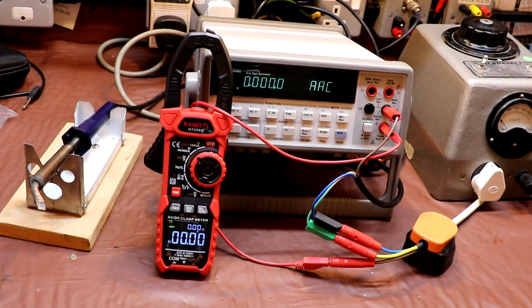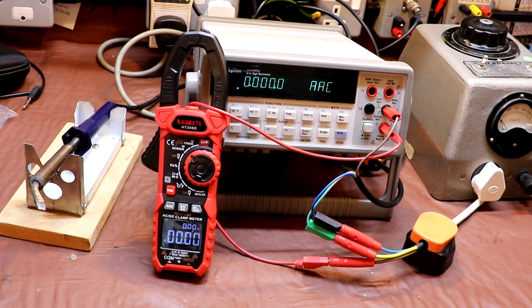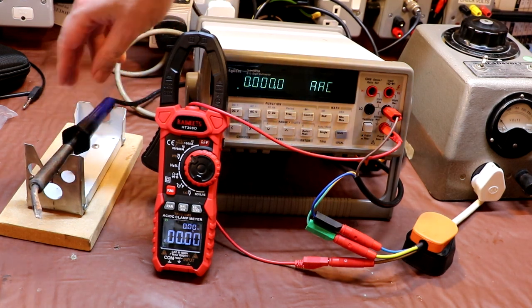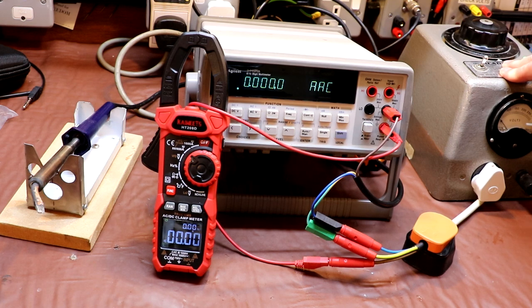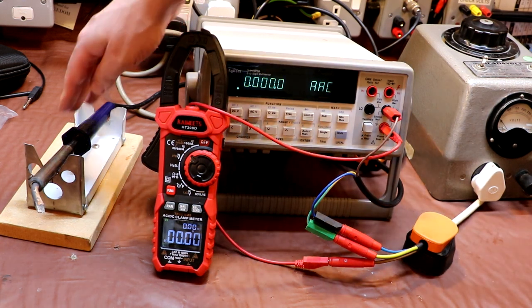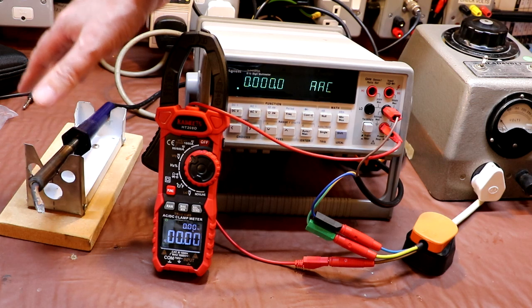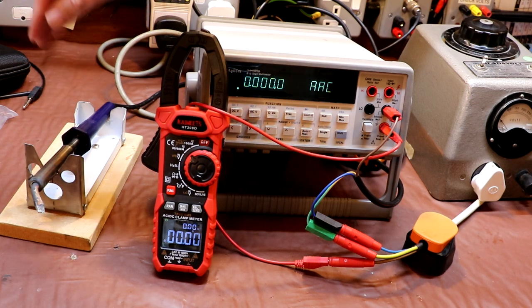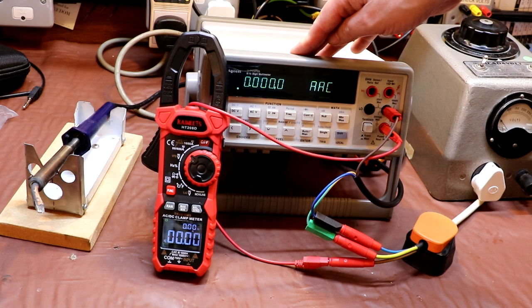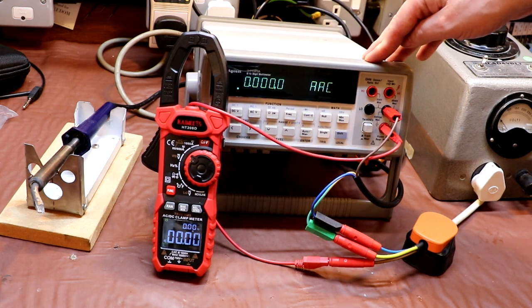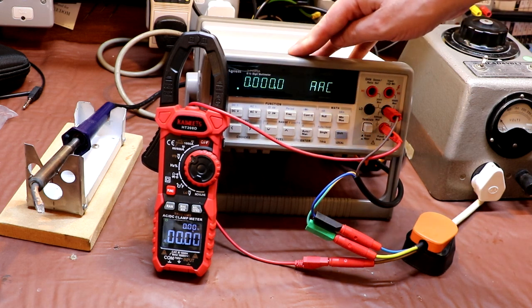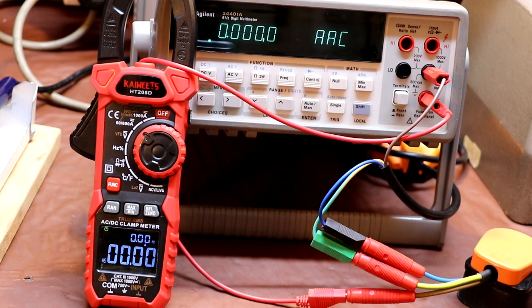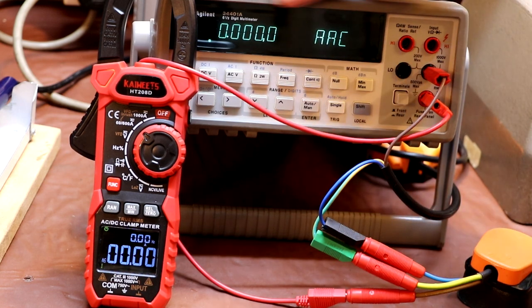I think we'll start off by taking a look at the very lowest AC current measurement that we can make. Now unfortunately I don't own anything as advanced as a current calibrator, so what we're going to do today, we're going to use this soldering iron as a load, and we're going to feed that load through a variac here so we can control the voltage going into the soldering iron. Because it's a resistive load, the current that it draws is going to be proportional to the voltage. And we're going to use our Agilent meter here, which is capable of making very accurate AC measurements. We're going to use this as a transfer standard. I'm going to start winding up the voltage now, and we should see the current increase on the Agilent meter here.